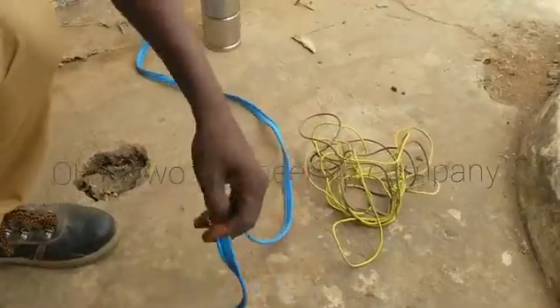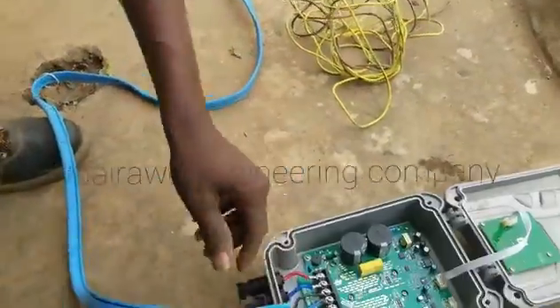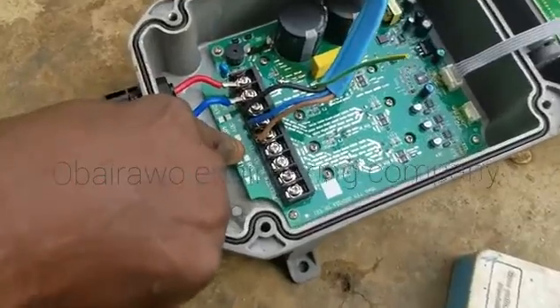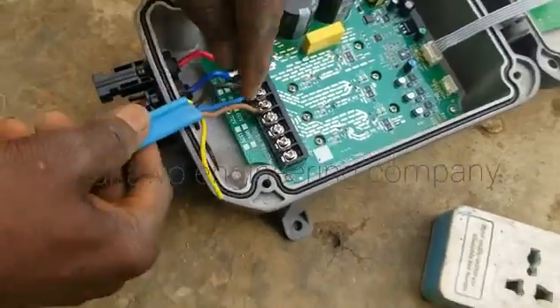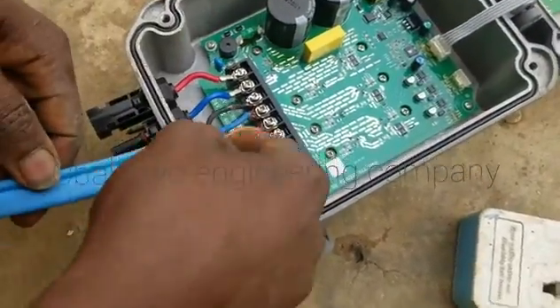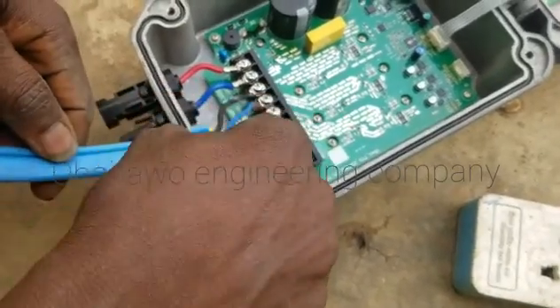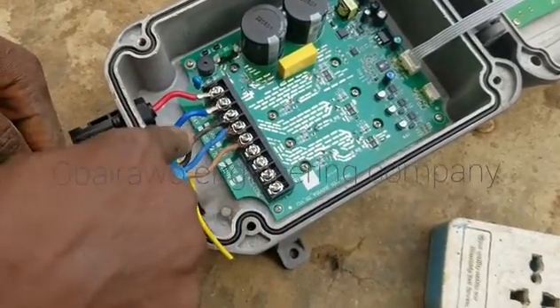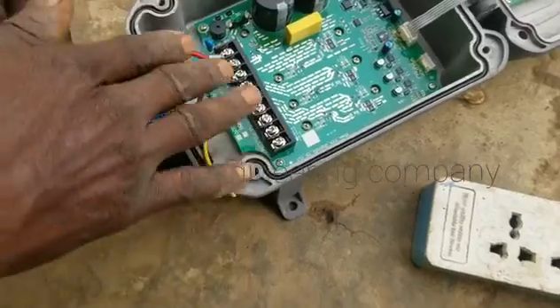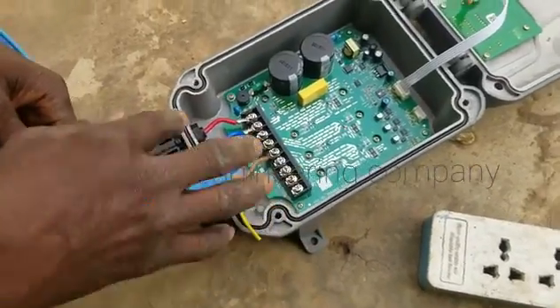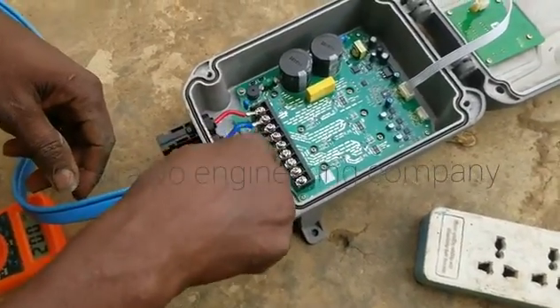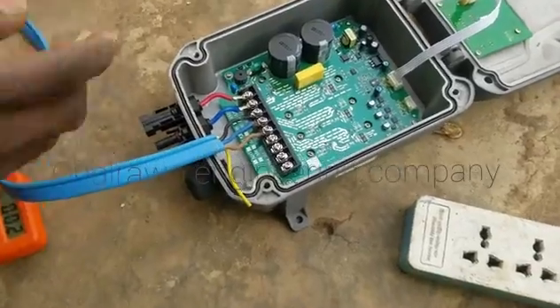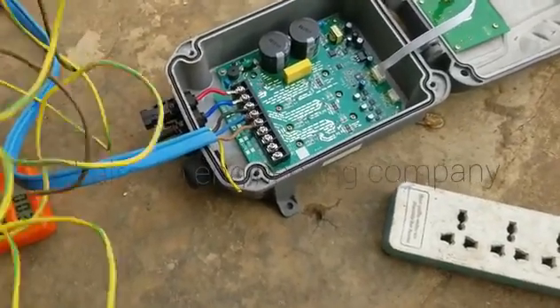The cable coming from the pumping machine is connected to the controller. The manufacturer did not indicate any specific code for this blue, black, and brown cable, so you can put them anywhere. If the machine spins to the wrong side, just swap two of these wires, and the machine will start spinning to the normal side.